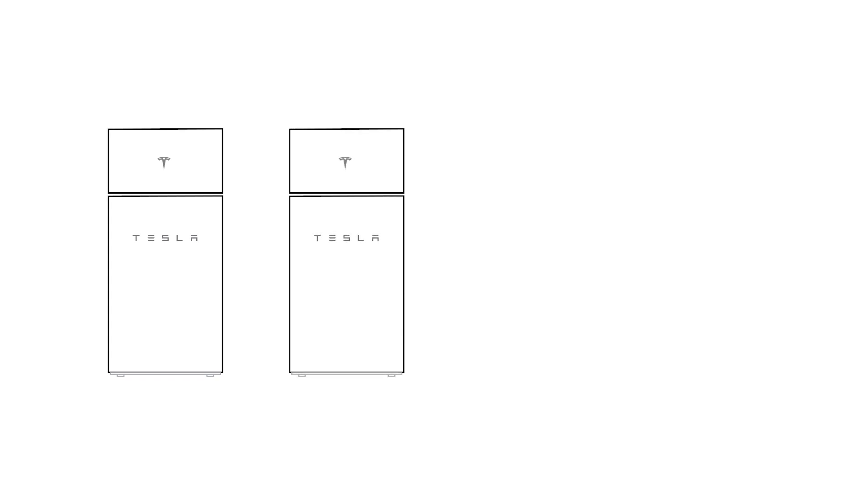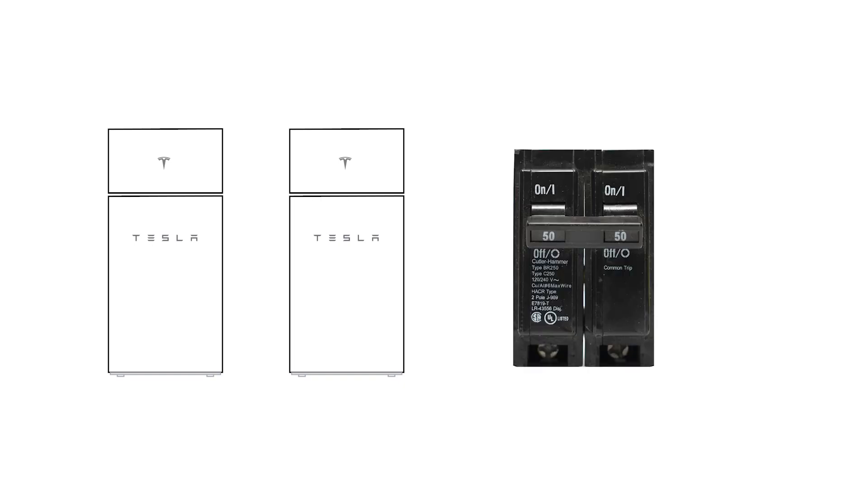Powerwall Plus can be installed with one additional Expansion Powerwall Plus. An additional Powerwall Plus requires its own AC circuit with a new 2-pole 50-amp breaker.